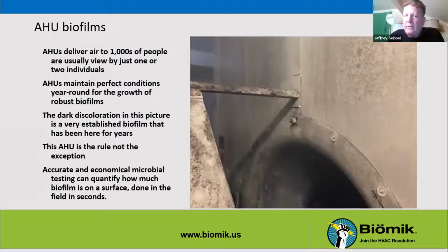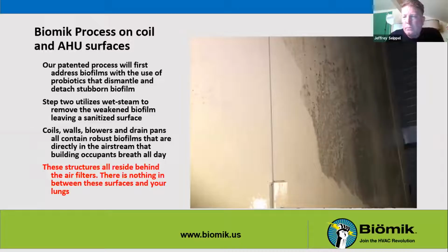So there is a need for an accurate and economic way to do microbial testing in air handlers to give you a quick way of telling where you're at as far as bioload. The Biomik process works perfectly in this situation. Our patented process first uses probiotics, which can break down the biofilm. The steam cleaning then removes the biofilm and adds a sanitizing step. So all the surfaces in the air handler can be cleaned, not just the coil. And the important thing to remember is that all these structures in the air handler are behind the filtration. So there's nothing standing in the way of the biology in your air handler and your lungs.